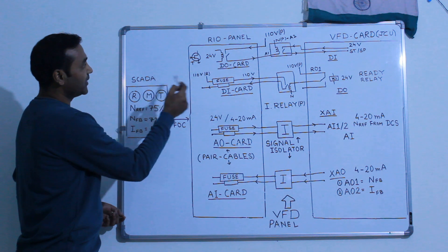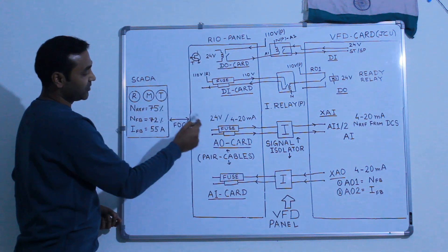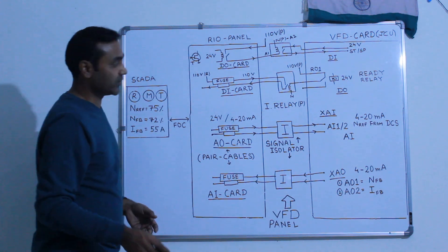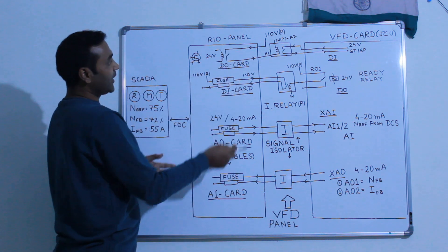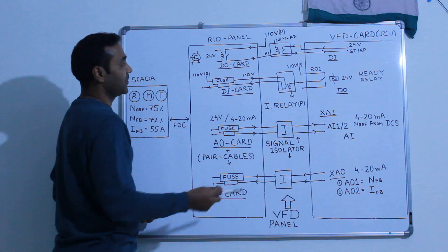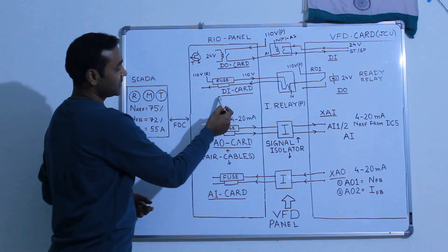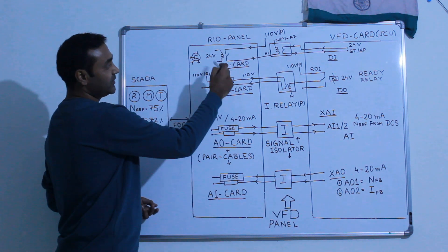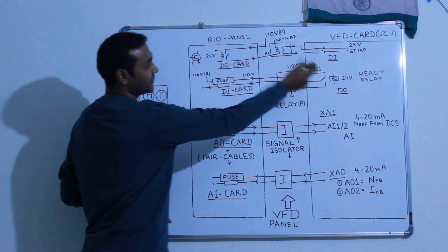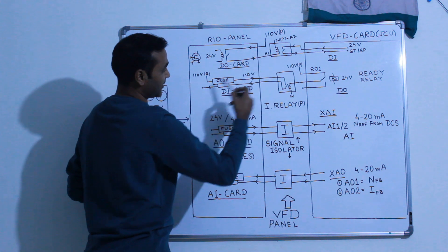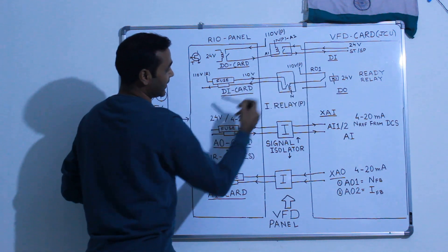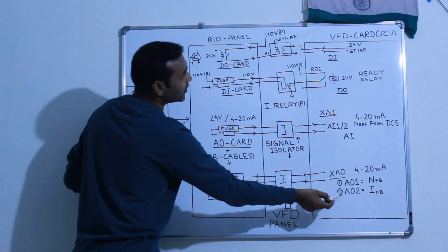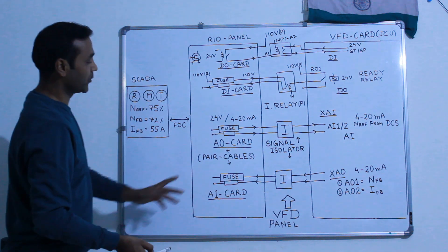Communication between SCADA or PLC and RIO panel happens with FOC, fiber optic cable. In the RIO panel you can see there are different cards - this is digital output card, this is digital input card, analog output card and analog input card. What is digital output for RIO panel becomes digital input for VFD, just vice versa. Here you can see DO-DI, DI-DO. Analog output becomes analog input for the card, and what becomes analog output for VFD card becomes analog input for RIO panel.